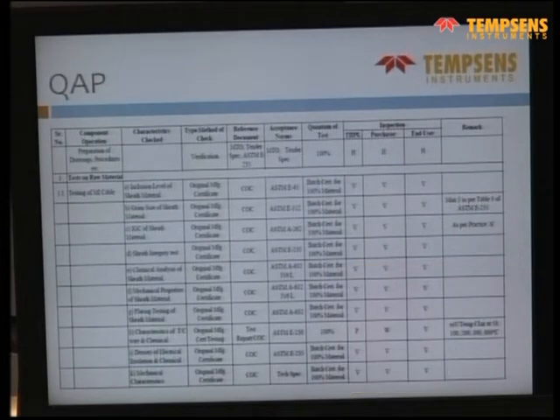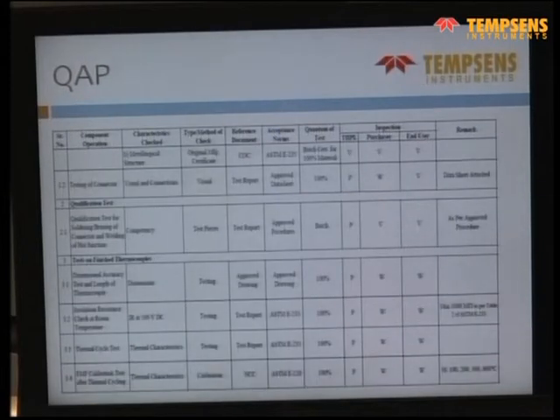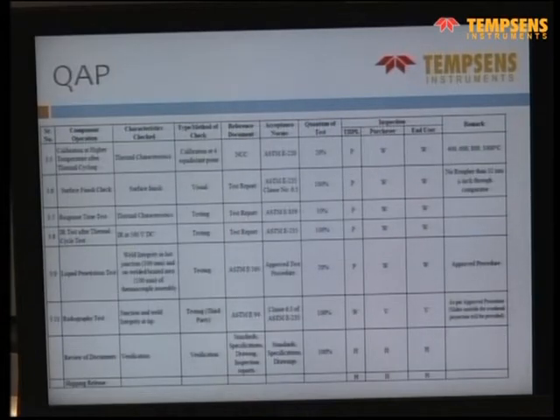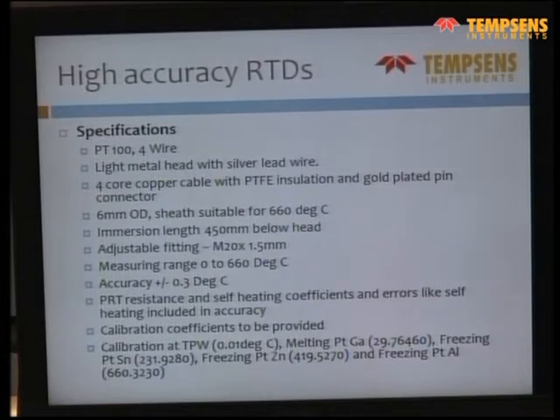We can see here there is a lot of testing on the MI cable as per ASTM E235. Then connector qualification, so the welder was qualified, and then dimensional, insulation resistance, thermal cycling, EMF calibration at 50, 100, 200, 300, 600 degrees centigrade. Then calibration at high temperature, surface finish, and all radiography, and 100% check for radiography. So there were a lot of checks for this particular customer and order.